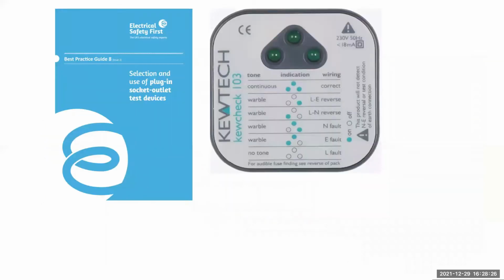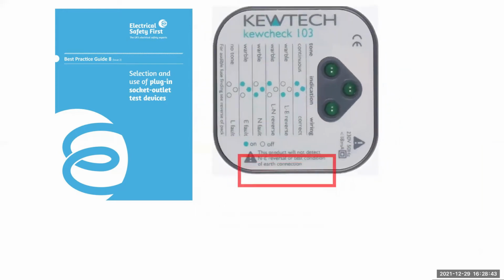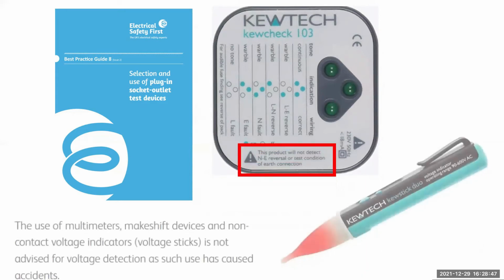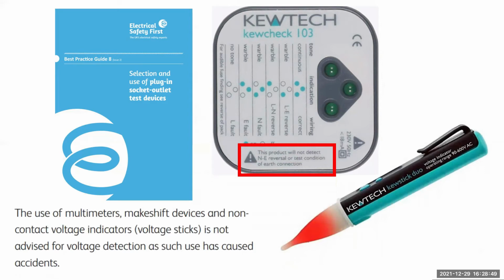Electrical Safety First have also brought out further guidance on the limitation of plug-in devices such as socket testers, as they are not suitable for safe isolation. A lot of people miss the key information on the front of the unit, as they are not capable of picking up a neutral earth reverse. The Best Practice Guide 8 also advises against the use of voltage sticks for safe isolation purposes as they are not reliable or accurate, and their use as such has caused accidents.